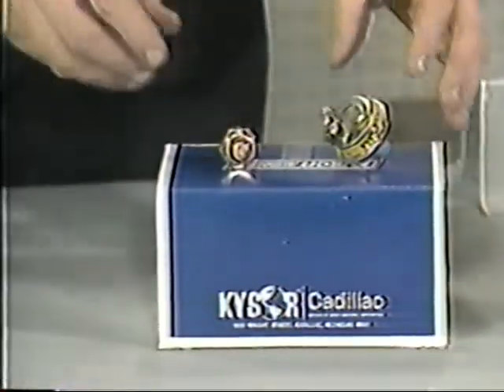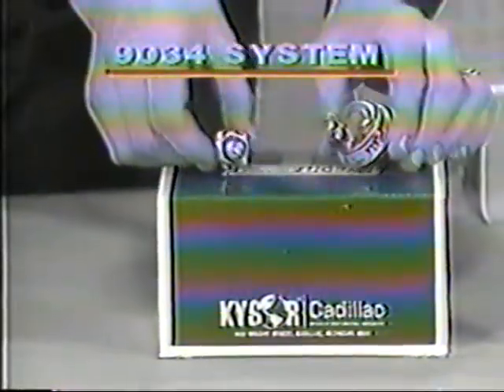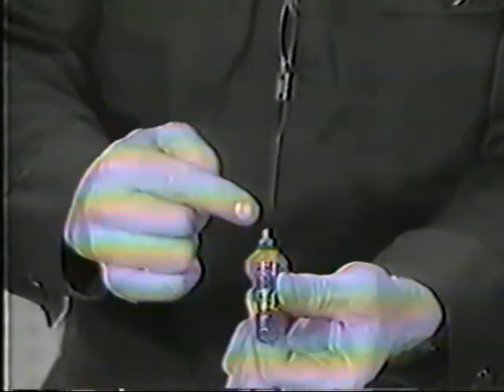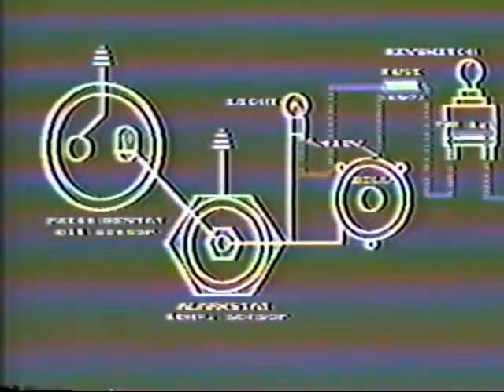Our first alarm-only system is Series 9034, which monitors engine coolant temperature and engine oil pressure. The two sensors have only one terminal apiece, and when the switches inside them open and close, they make or break a connection between the terminal and ground. The 9034 circuit begins at the key switch and runs through the system fuse to the light and bell, so they both have 12 volts.